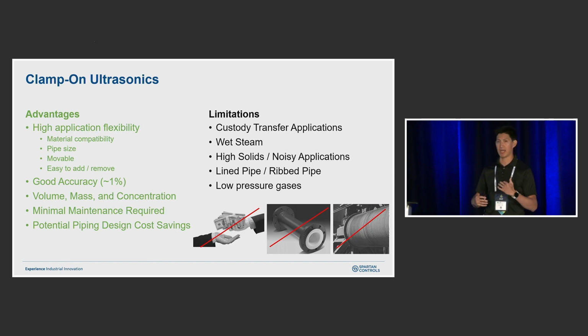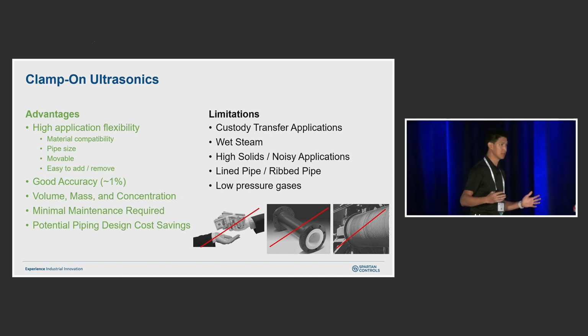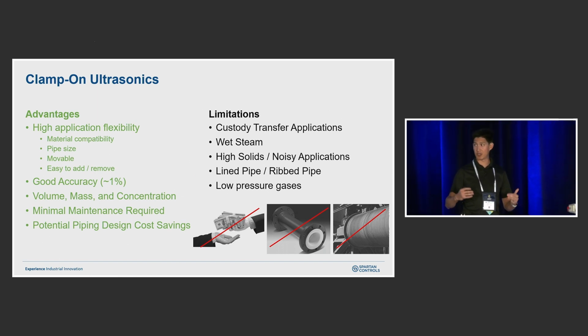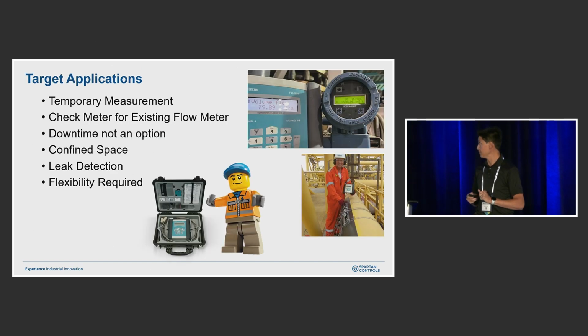And anytime the pipe is not uniform. So what that means is if we have a pipe that's ribbed, it becomes very difficult to put transducers on, or if the pipe has a lining in it, we can't always be sure that the lining is uniform all the way through and also doesn't have an air gap between the liner and the pipe. Okay, so those are kind of the limitations there.